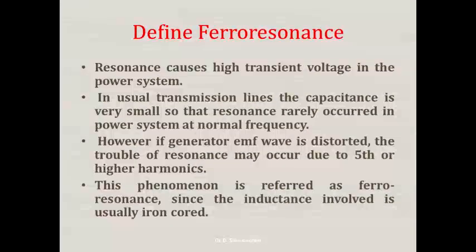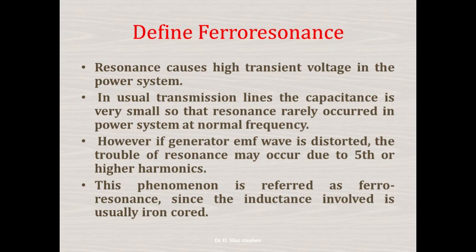Define ferroresonance. Resonance causes high transient voltage in the power system. In usual transmission lines the capacitance is very small, so resonance rarely occurs at normal frequency. However, if the generator waveform is distorted, the trouble of resonance may occur due to fifth or higher harmonics. This phenomenon is referred to as ferroresonance, since the inductance involved is usually iron-core.